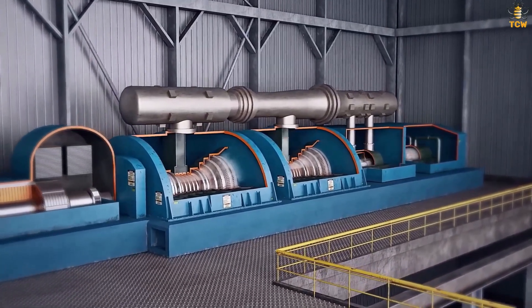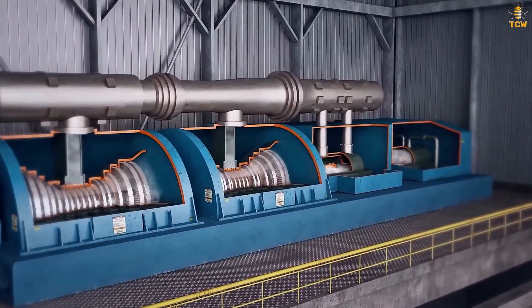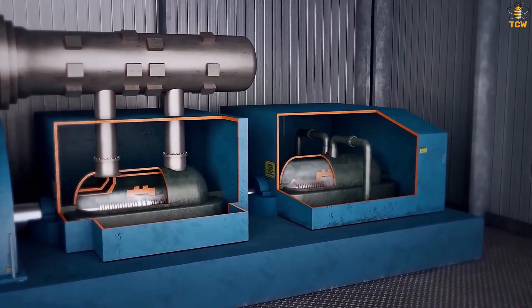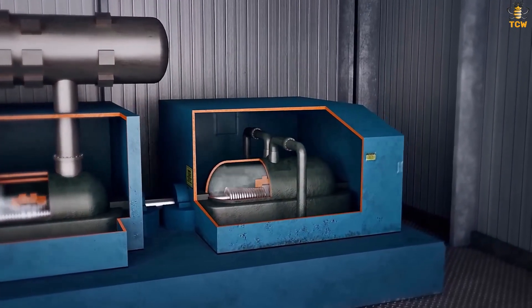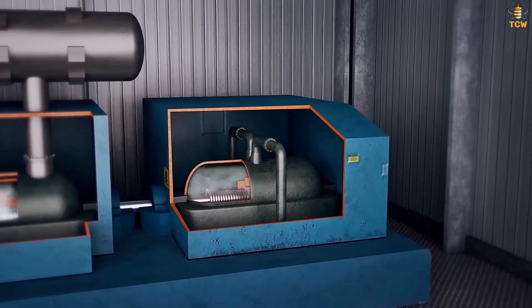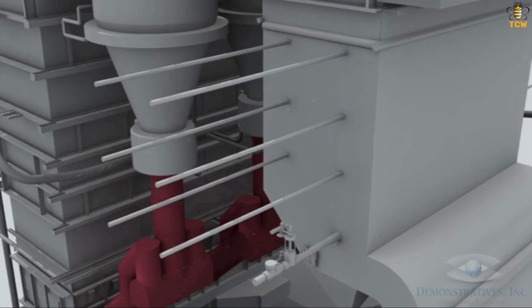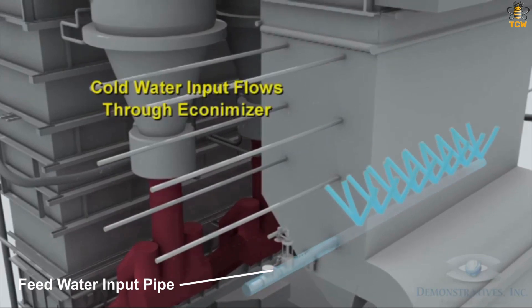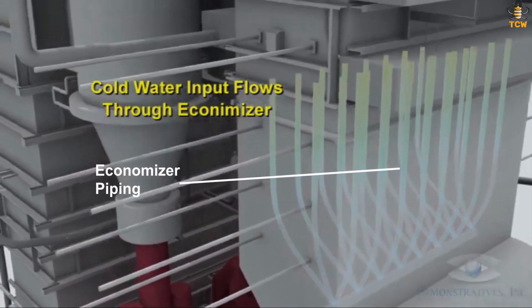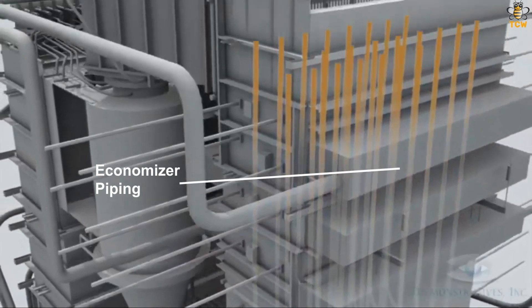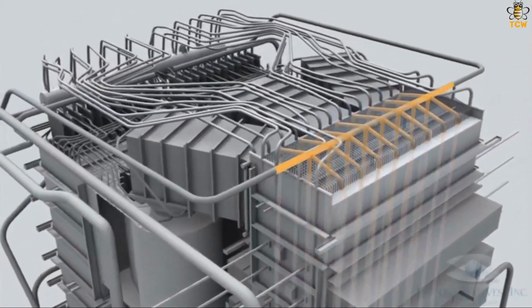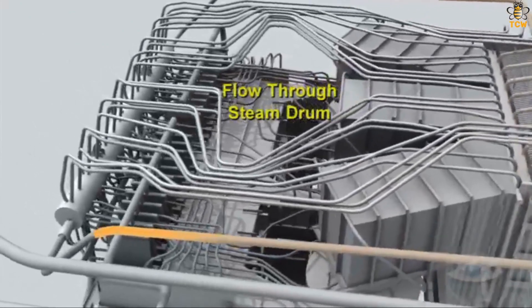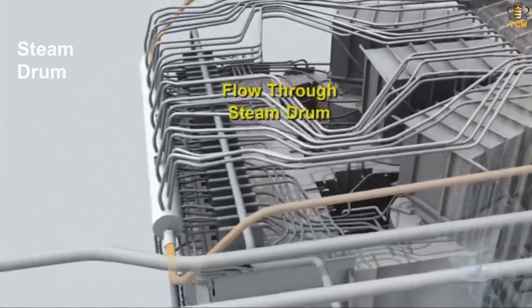Next, we will explain the flow of water from the steam condensation process coming out of the turbine. The steam that comes out of the turbine will condense and become water. This water is then pumped to the boiler and called feed water. This feed water then flows into the economizer pipe. The hot coal burning gas flowing through the economizer has a cooler temperature because heat has already been absorbed by the superheater and reheater sections. This hot gas heats the feed water in the economizer but does not bring it to its boiling point. The heated feed water then flows into the steam drum.